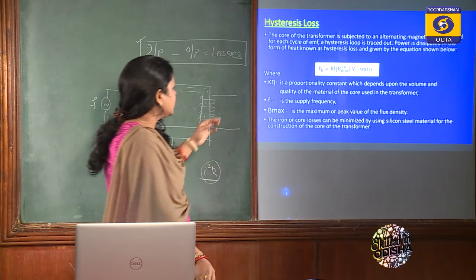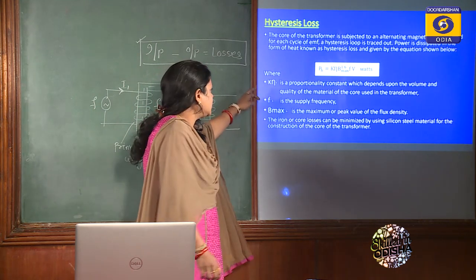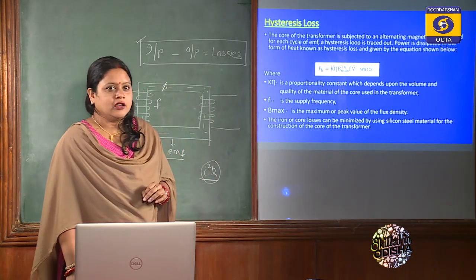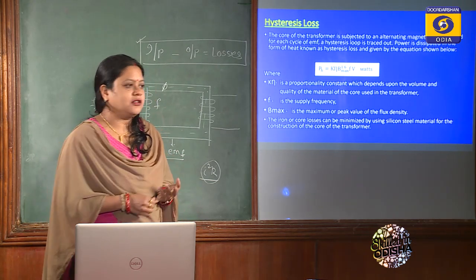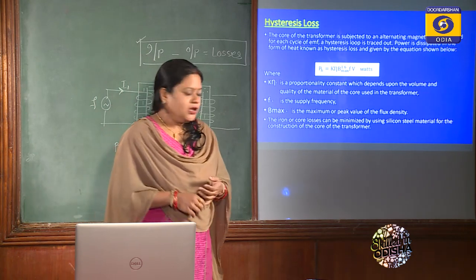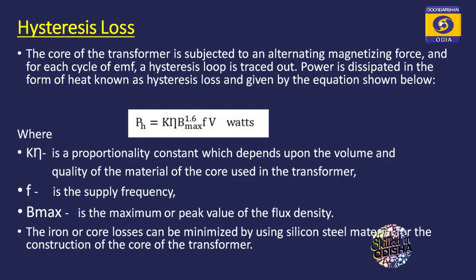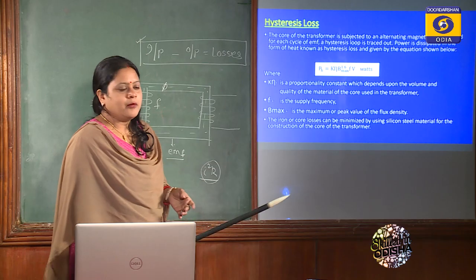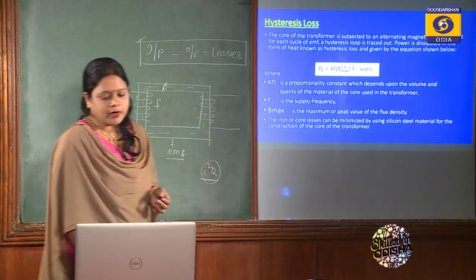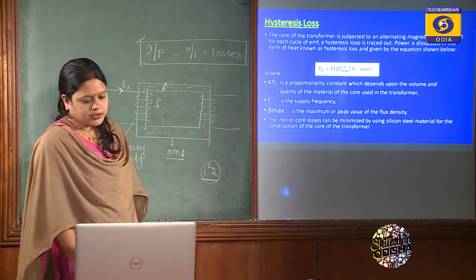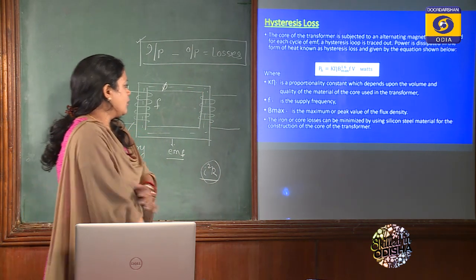The hysteresis coefficient Kη is very small for silicon steel. Therefore, transformer cores generally use silicon steel rather than iron. F is the supply frequency and Bmax is the maximum or peak value of the flux density. Hysteresis loss can be minimized by using silicon steel material for the construction of the core.